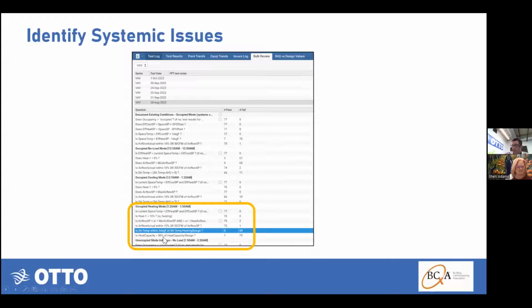Asking an easier question right below that: is heat capacity measured in the field? We look at the airflow reading from the box and the discharge temperature off its parent air handler, so we can calculate the heat capacity live for every single reheat coil and compare it to design. Here we're asking, was it at least more than 50% of design capacity? The answer was no on almost every single one.